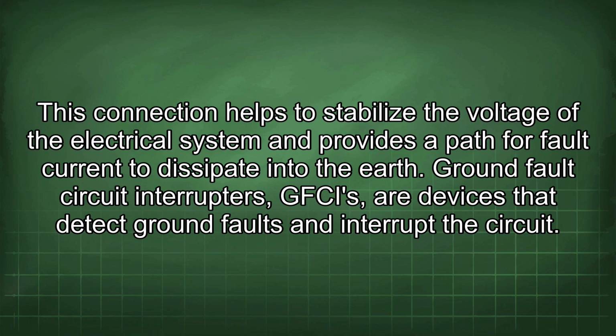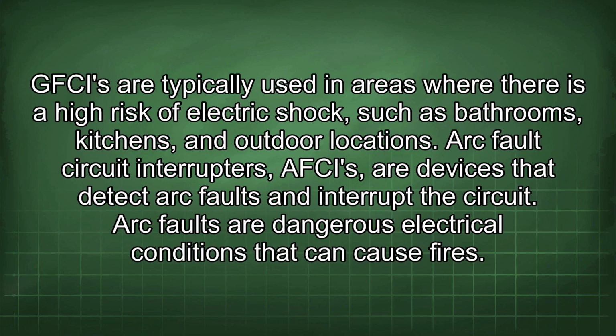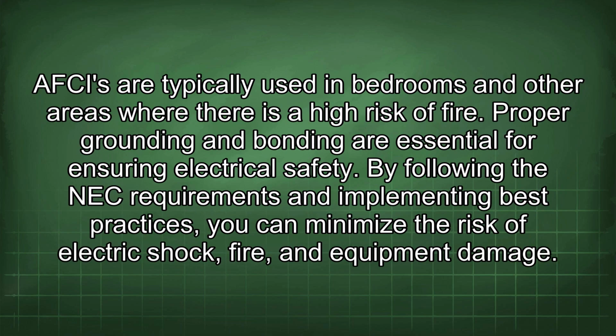Ground fault circuit interrupters, GFCIs, are devices that detect ground faults and interrupt the circuit. GFCIs are typically used in areas where there is a high risk of electric shock, such as bathrooms, kitchens, and outdoor locations. Arc fault circuit interrupters, AFCIs, are devices that detect arc faults and interrupt the circuit. Arc faults are dangerous electrical conditions that can cause fires. AFCIs are typically used in bedrooms and other areas where there is a high risk of fire.